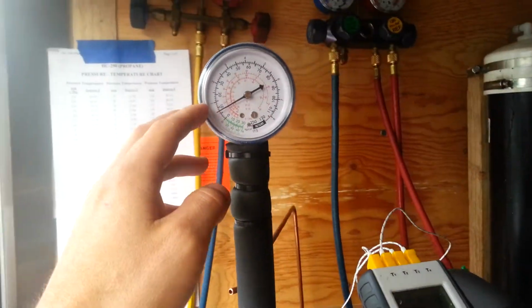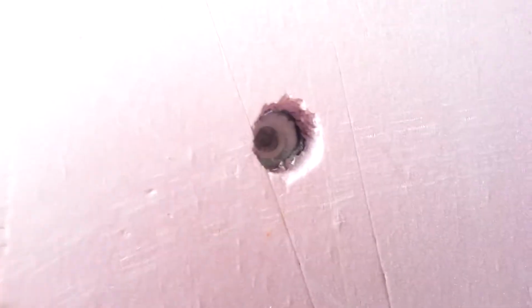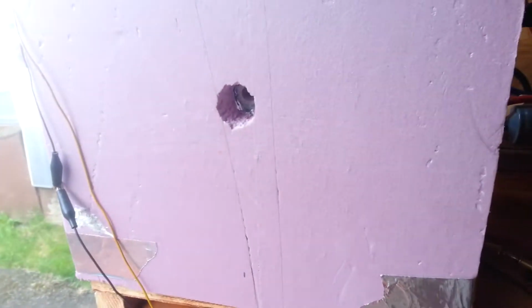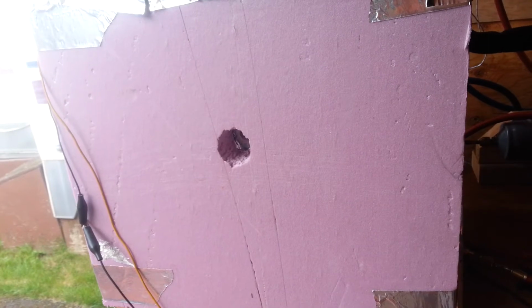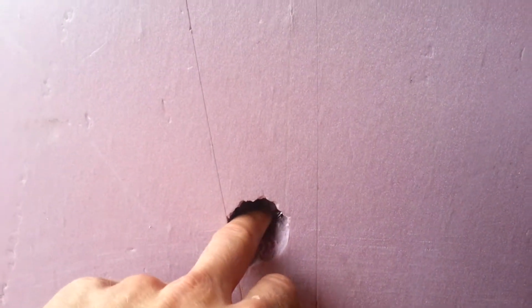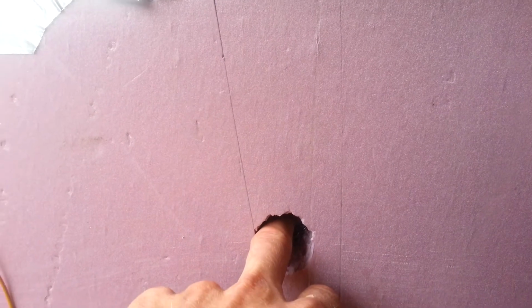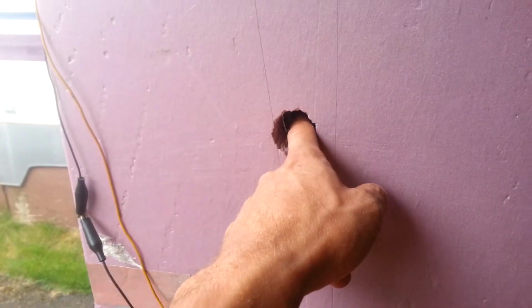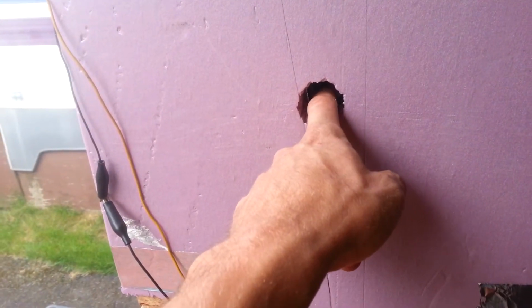Now, the same thing can happen with this thing. If I crank this thing down, even at this low pressure, I can't demonstrate it for you on the sight glass very well, but it is going to dry this thing out a little bit. The liquid level is going to drop because more refrigerant is being carried away to the compressor. What I was surprised to find was that above zero, above about 10 degrees Fahrenheit, just about any point at which I would adjust this throttle, I would see the liquid level more or less be maintained right around the height of that sight glass. I was a little bit surprised to see that, but on the other hand, there might be a perfectly good reason for it.